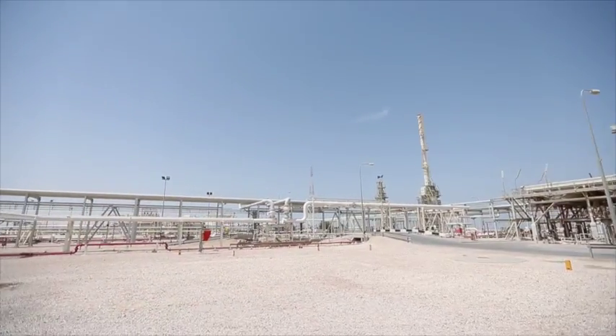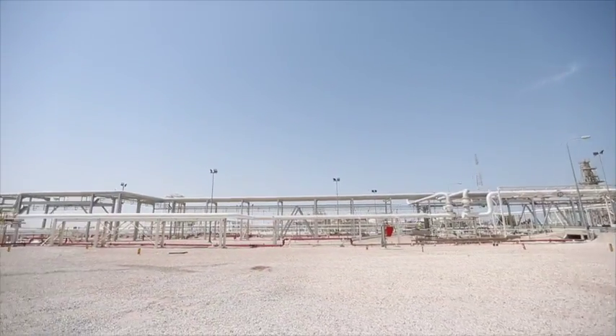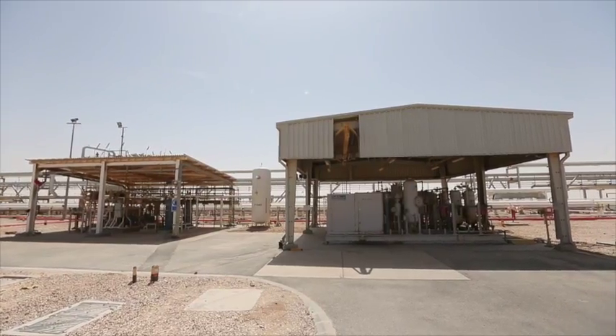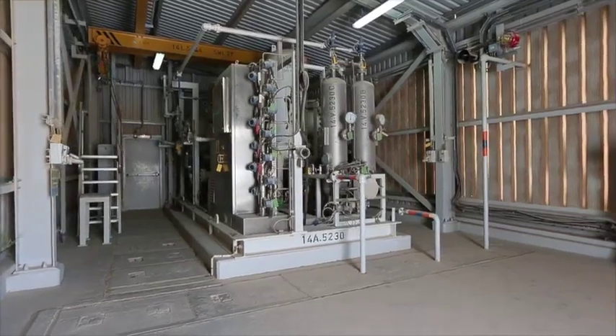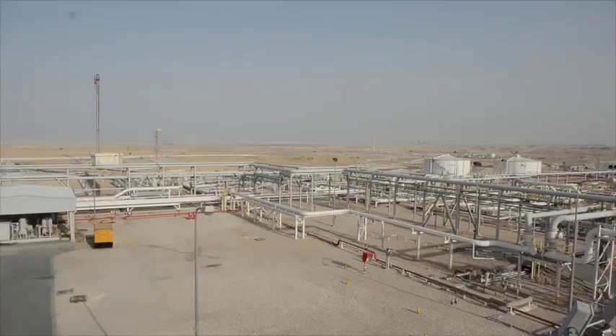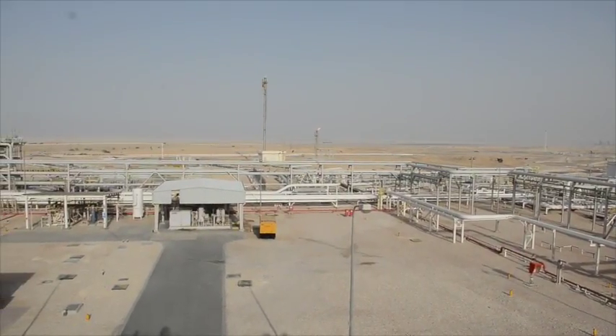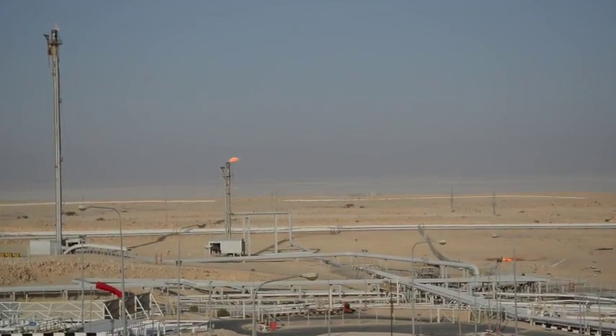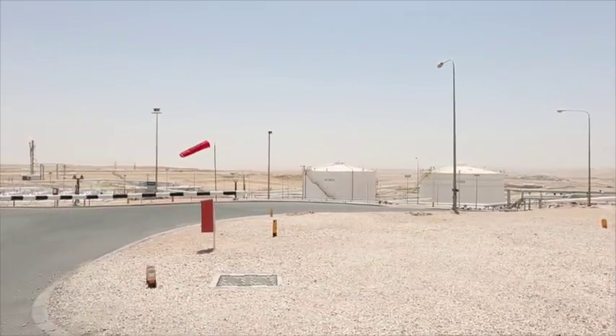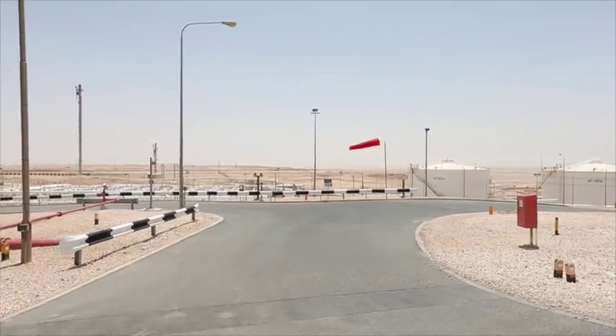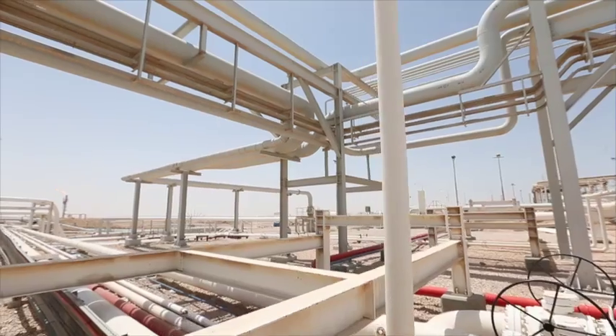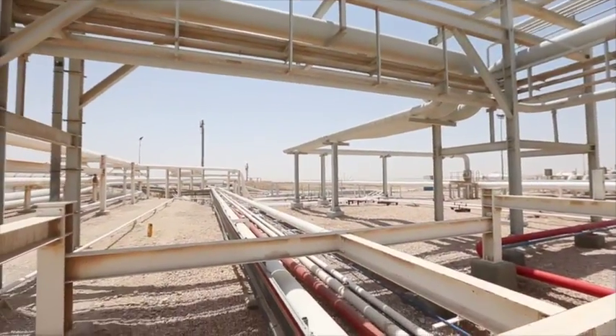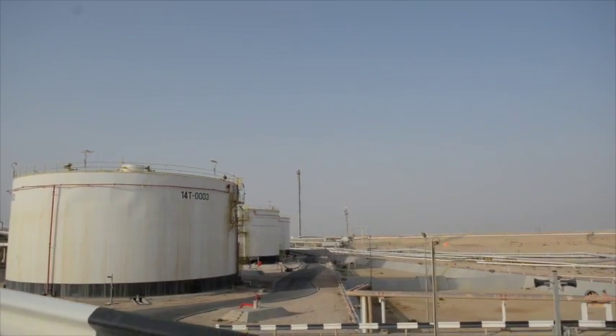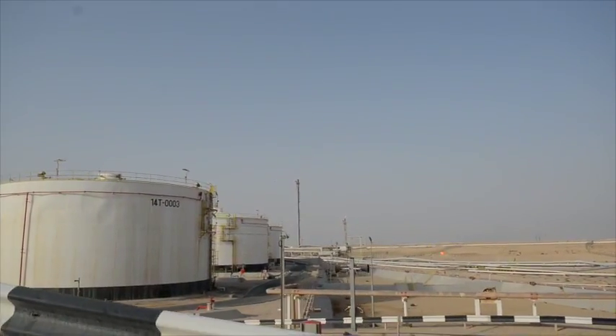Three instrument air systems work in concert at the Fahahil main degassing station. The first two systems supply the main plant, while the third is exclusive to the gas lift modifications. The Fahahil main station is serviced by three flare systems, all of which are located outside of the perimeter fence and continuously purged with fuel gas from the government gas line. Pressure relief from the plant's safety release valves, blowdown valves and pressure control valves, as well as instrument, equipment and pipework vents, is gathered into a 30-inch flare header, which passes to the flare area outside the station perimeter.